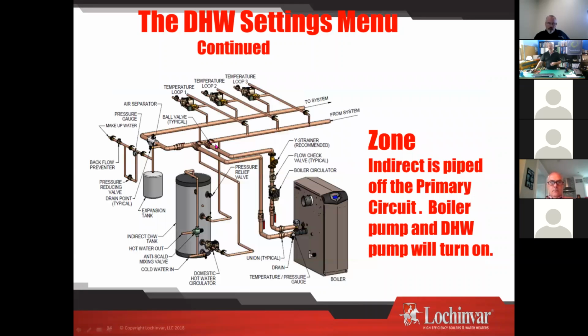Your other option is to pipe as a zone. And I apologize, it's a pretty busy drawing here, but in that case, my domestic hot water is piped up here, just like another zone of heat. And what my boiler now knows is, hey, keep that boiler circulator on and put the hot water up on the loop so that the domestic hot water circulator here can pull it down. One of the advantages to domestic as a zone is the fact that you do heating and domestic hot water simultaneously. You're going to put the water up there on the loop.